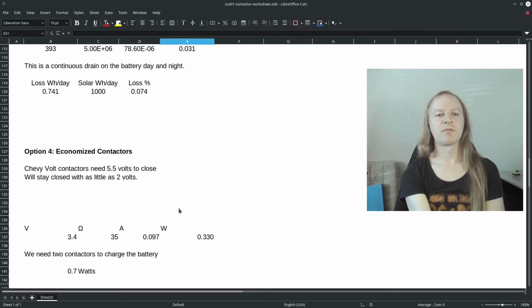Using the same 35 ohms with Ohm's law, we find 0.097 amps, or 0.33 watts. Since we need 2 contactors to charge the battery, we're looking at 0.7 watts lost operating the contactors at a reduced voltage.